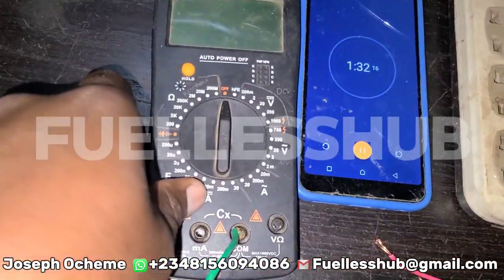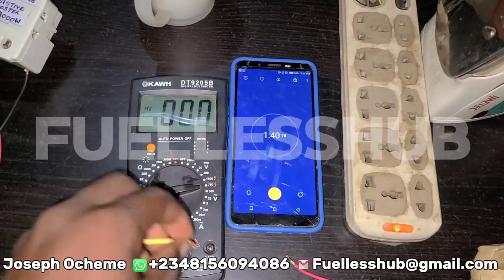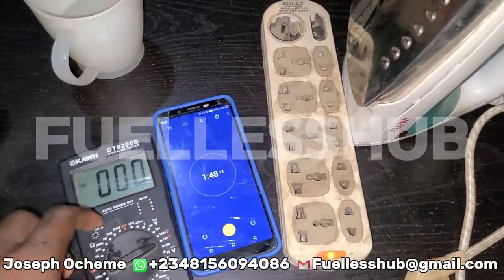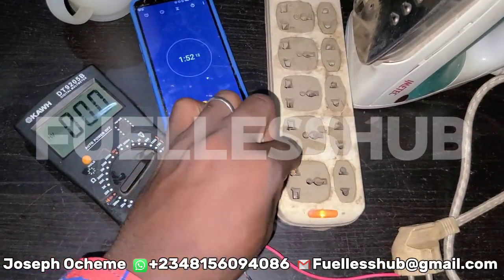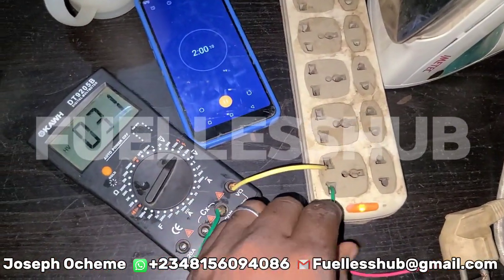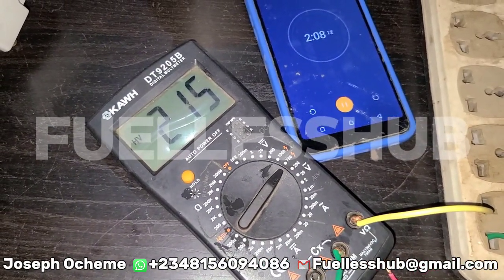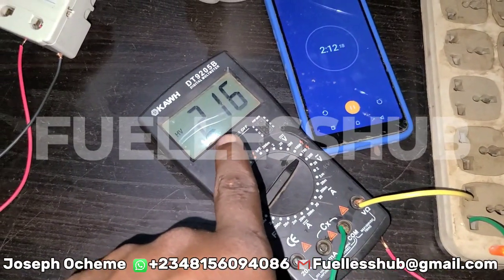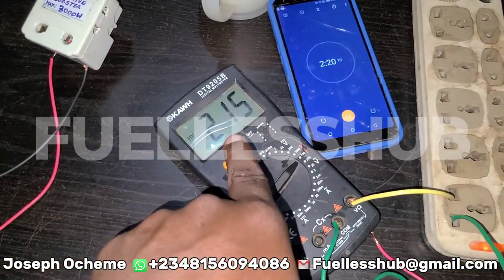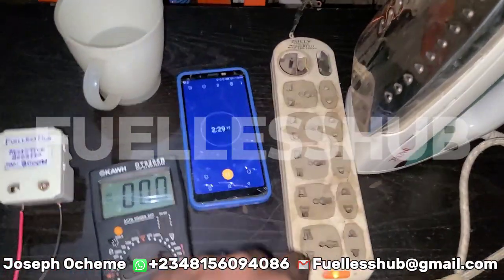On this supply, I'm using the multimeter set to 750 volts. I'm using one hand to do this because this is not a professional video. Let's check the voltage quickly. The voltage is reading 214, 216, 215 volts — fluctuating between 214 and 216. So let's stick with 215 volts. We are sure of the voltage entering this system.